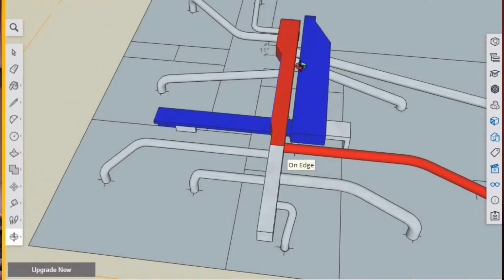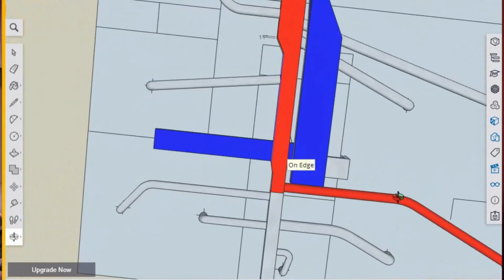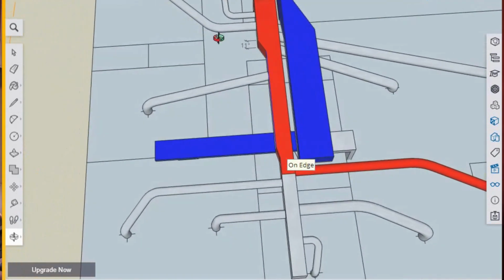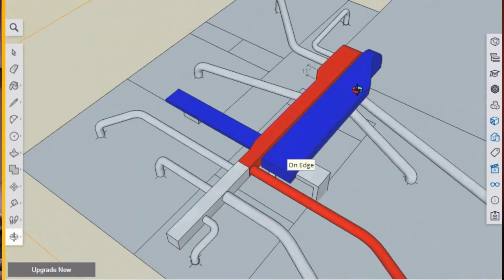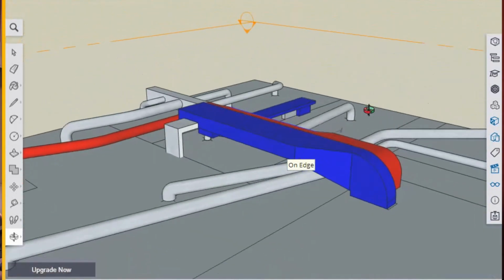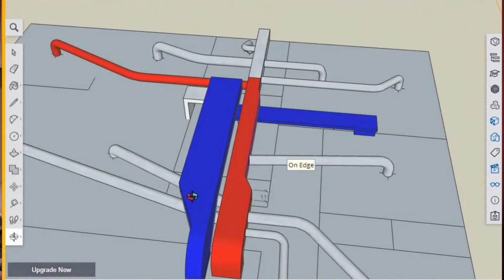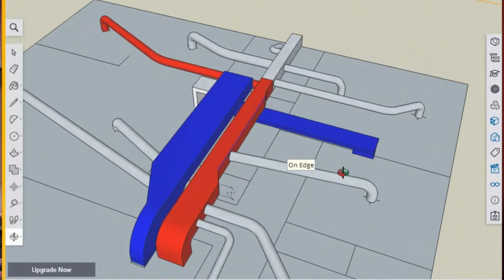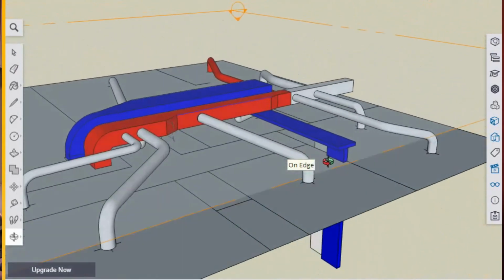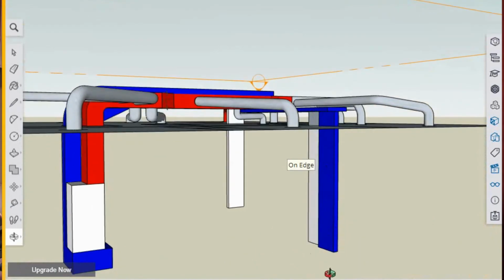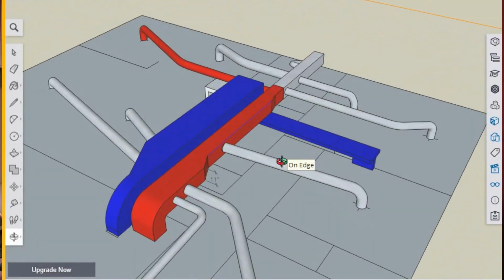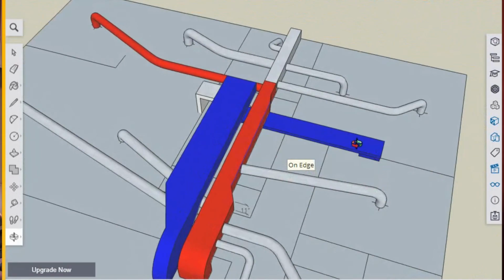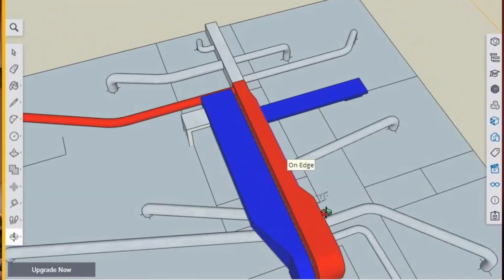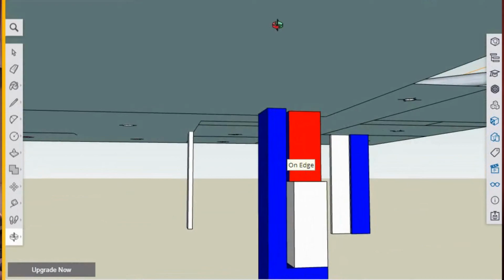So I have colored my critical path, the furthest supply from my system, in red, okay, which happens to still be that kitchen up in the upper right-hand corner. Or I'm sorry, the upper left-hand corner. So this is our critical path on the supply. Our return critical path, notice we have individual returns here, is this middle bedroom. Our middle bedroom is going to have the furthest return. It will come up across into a main trunk and then back down to the unit.